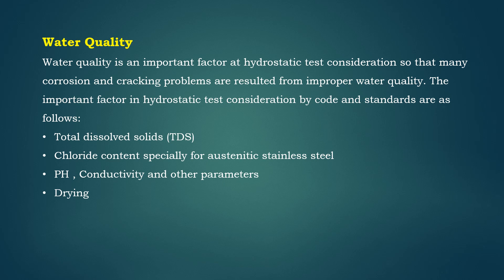Water quality is an important factor in hydrostatic test consideration, as many corrosion and cracking problems result from improper water quality. The important factors in hydrostatic test consideration by code and standards are as follows: total dissolved solids (TDS), chloride content — especially for austenitic stainless steel — pH, conductivity, and other parameters.